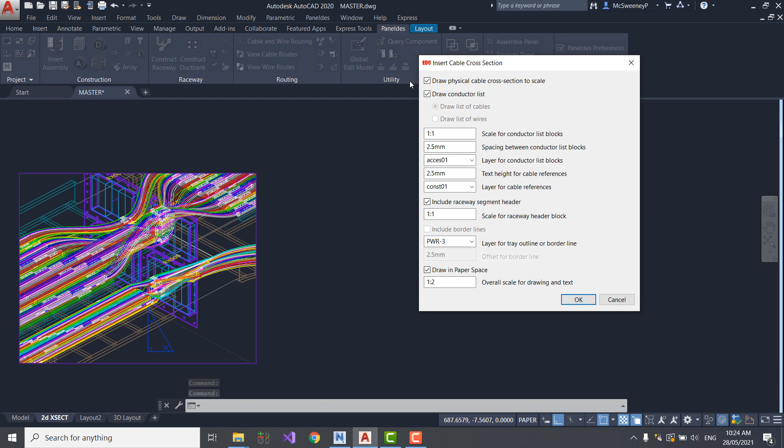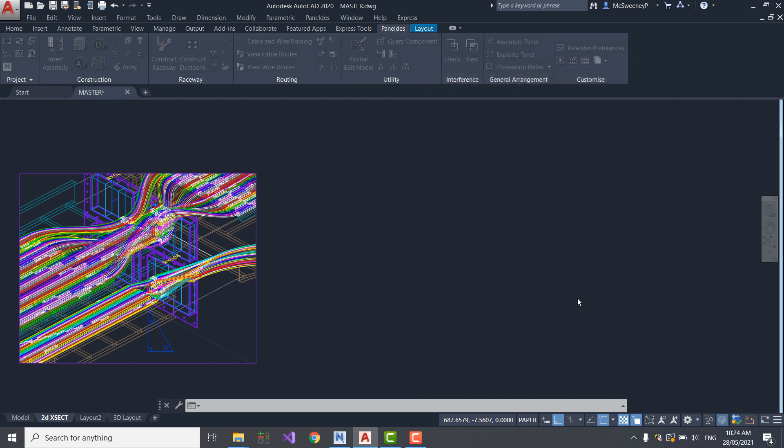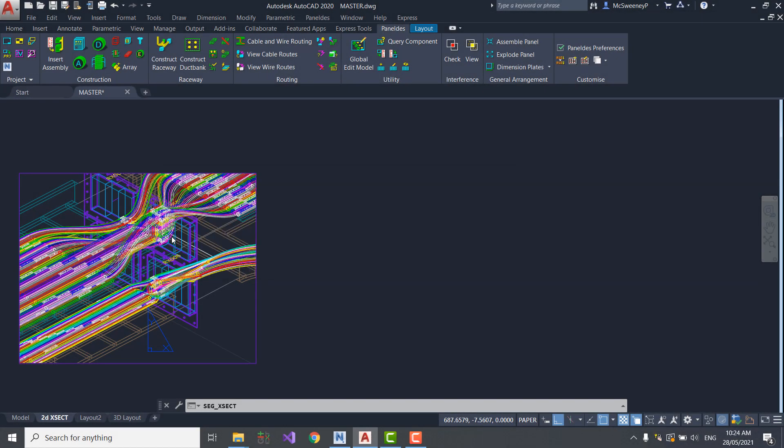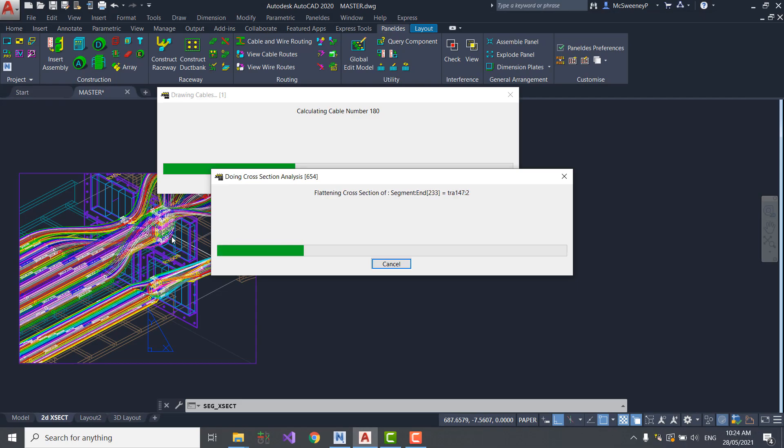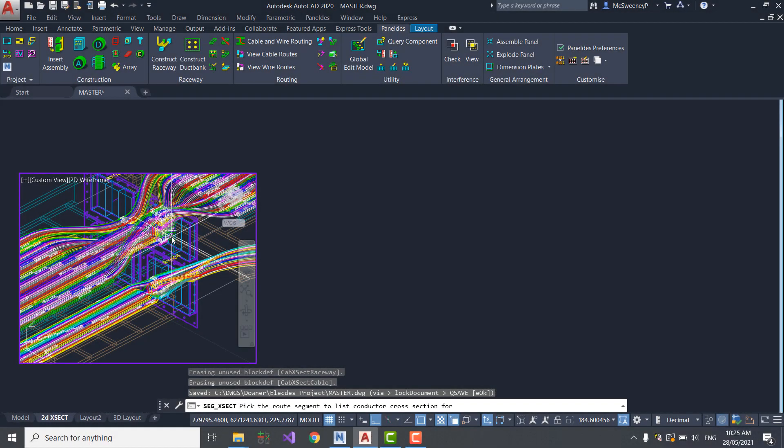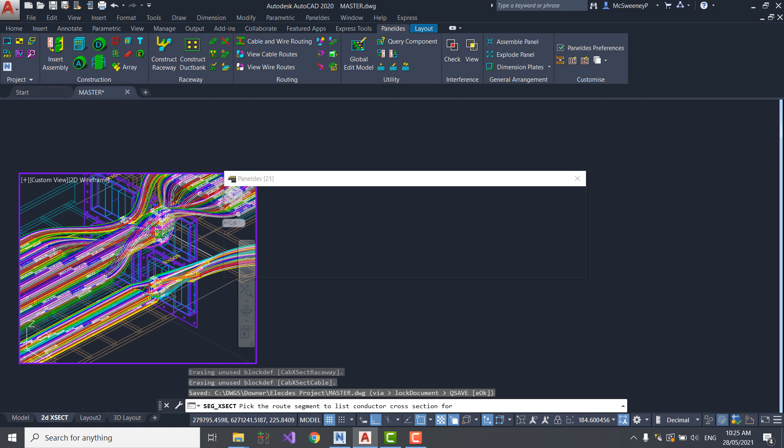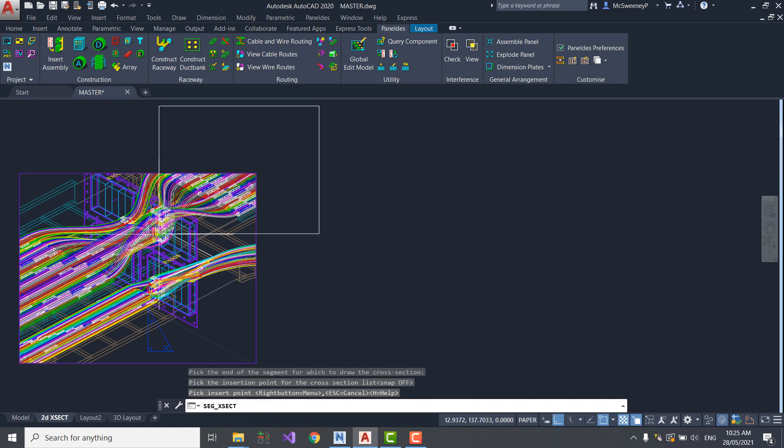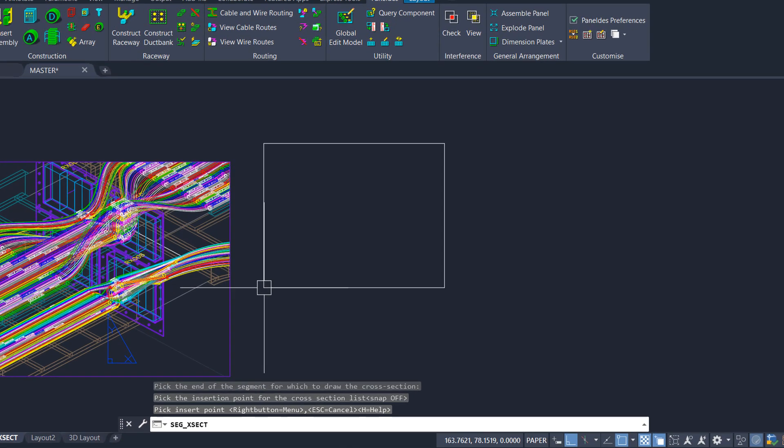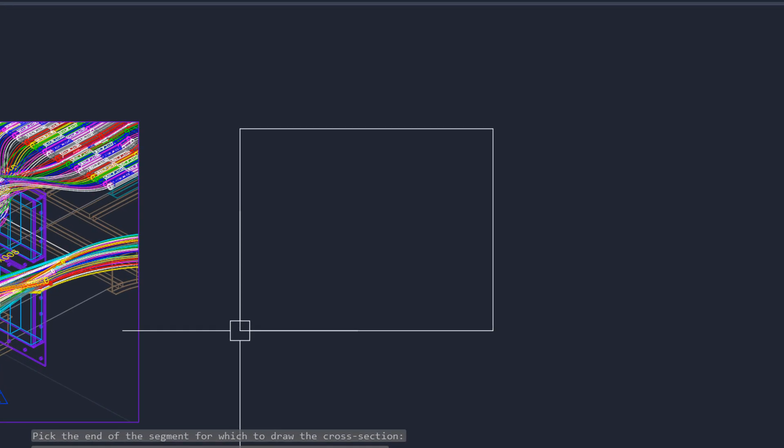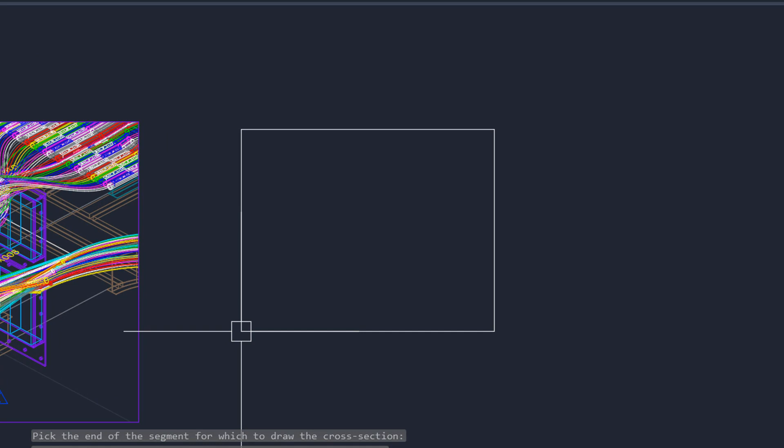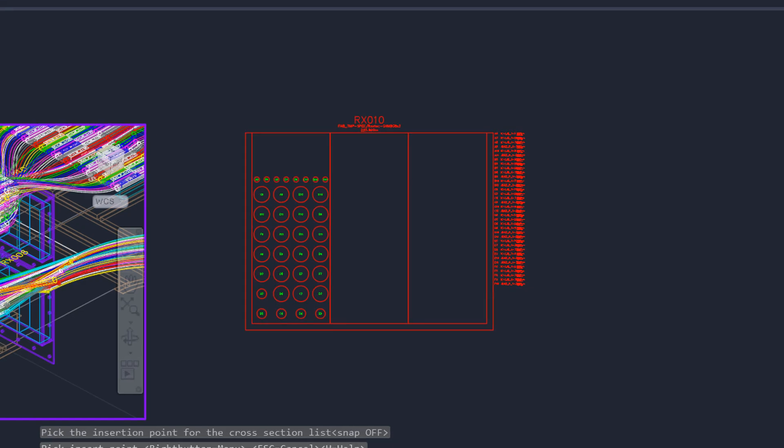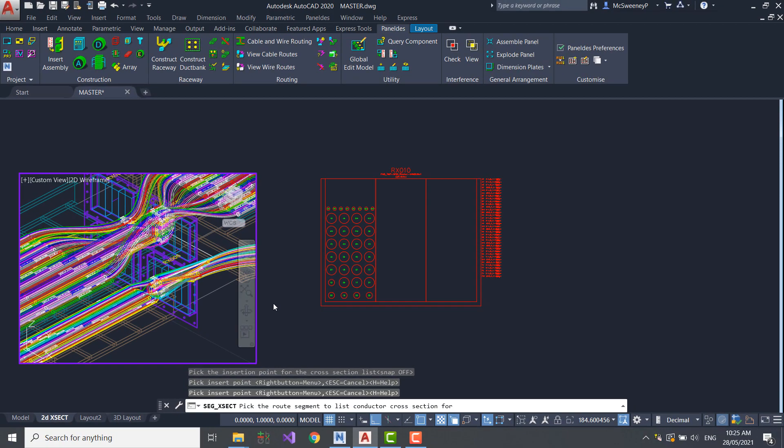Before construction, I just need to confirm the construction scales, and other parameters such as layers and colors. Let's select RX10. I just need to select the centerline, and the end from which I want to view the cross-section. I'm now going to drag RX10 into position. The cables are drawn just as they would be placed in the transit. The circles represent the cable diameters, not the block size.